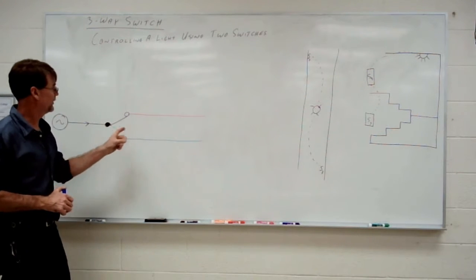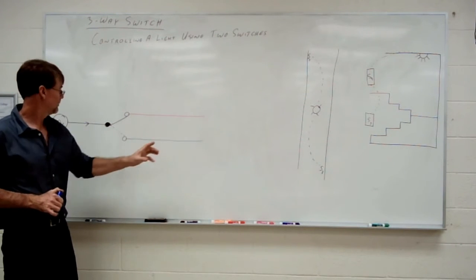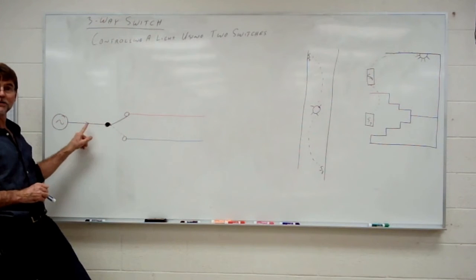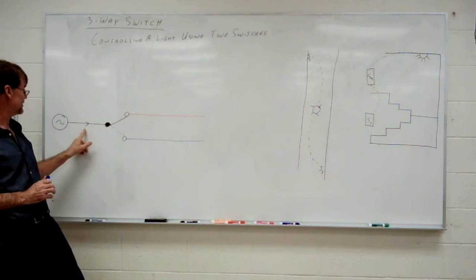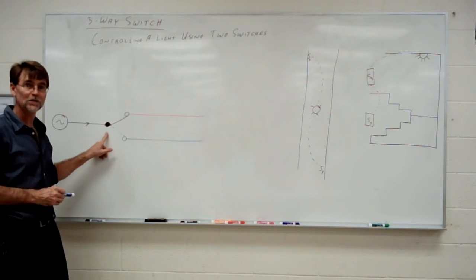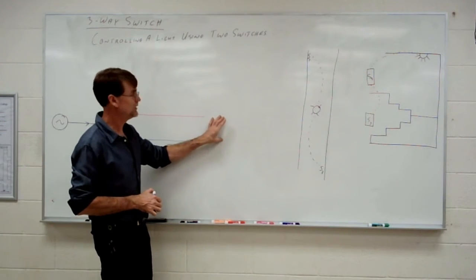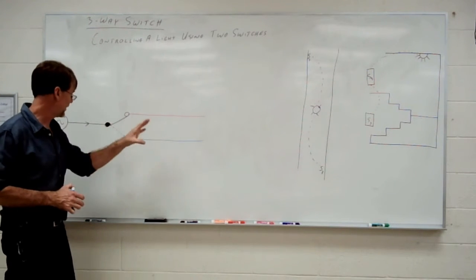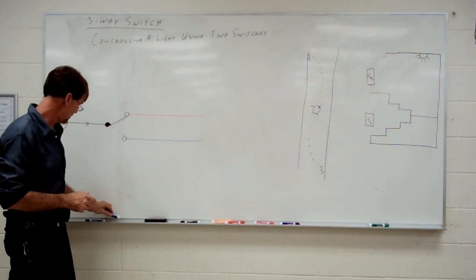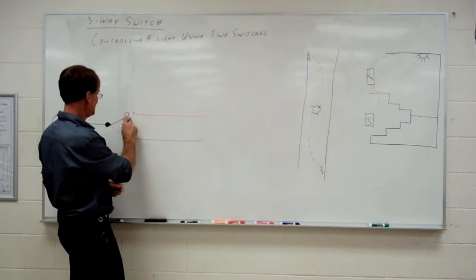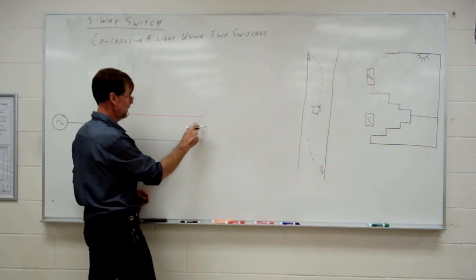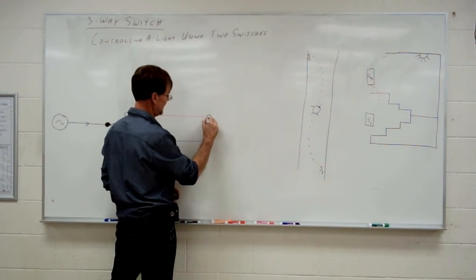The second one, we're going to turn it around. So the common here, I call it the input. The common is the line side of this switch. The second three-way switch, however, when we pair these up, is going to get turned around so that these two other terminals become the line side.